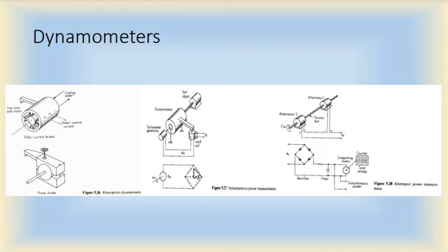And the bridge output is directly proportional to this excitation voltage, and it is also proportional to the torque. Torque is the output of the load cell. So this output voltage, that is E naught, is actually an instantaneous power signal. If we can measure this instantaneous power signal, this E naught, by some means, then we can calculate the power. So this is one method of direct, or automatic, measurement of power from the system itself.